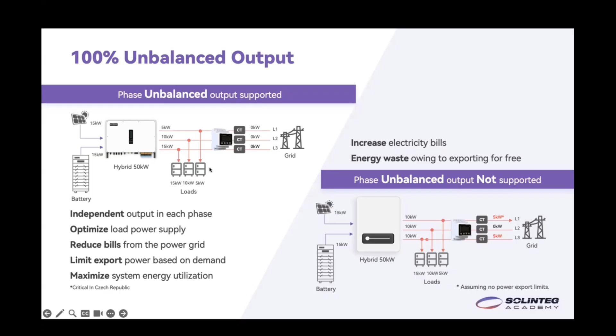In this case, we can send independent output in each phase. For example, we can look into the diagram here. Now the device needs 5 kilowatt power, and we can just send 5 kilowatt power to it. And for the device that needs 15 kilowatt power, we can send the required power directly to this device, so that we can help to optimize the load power supply without increasing our electricity bills or wasting any generated energy. And in this case, we can maximize the system's energy utilization by having this 100% unbalanced output.